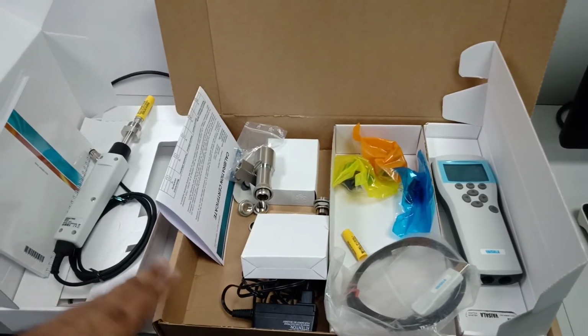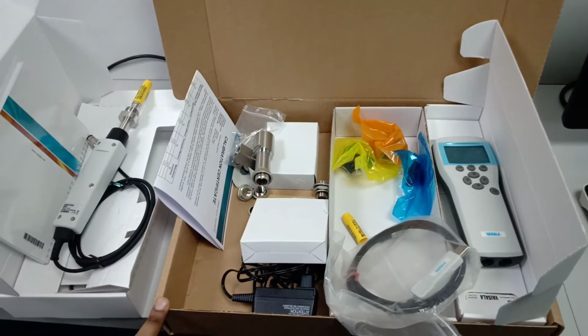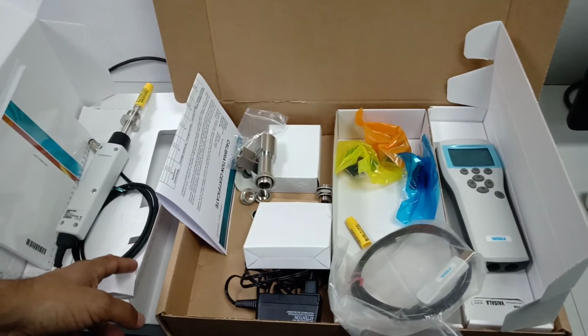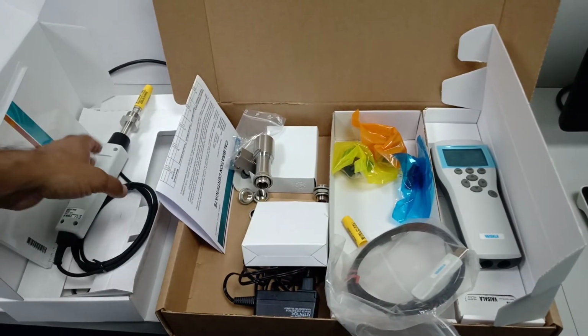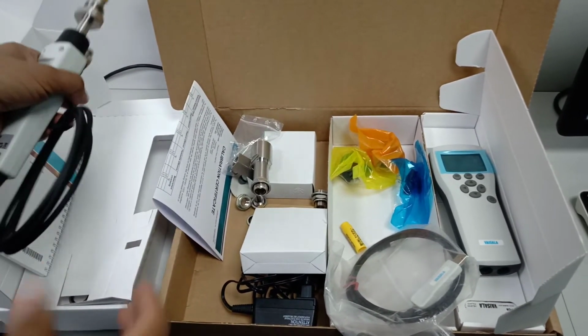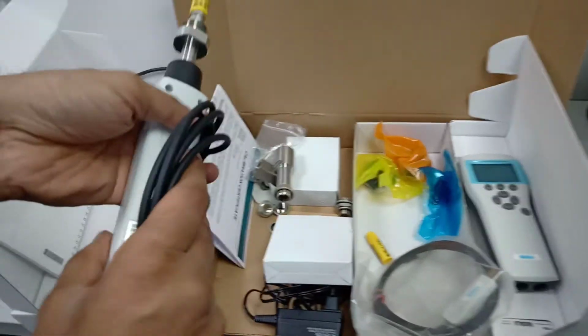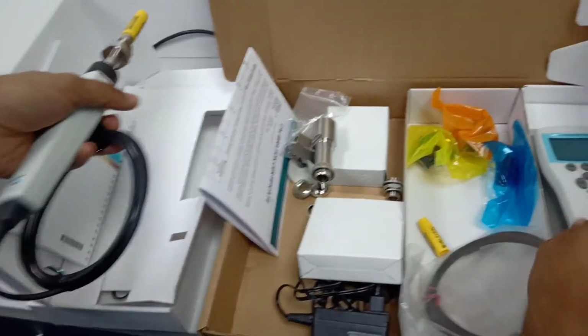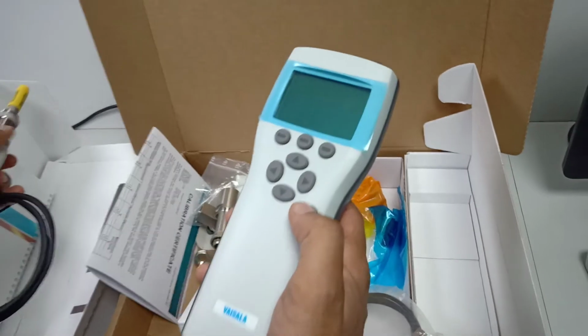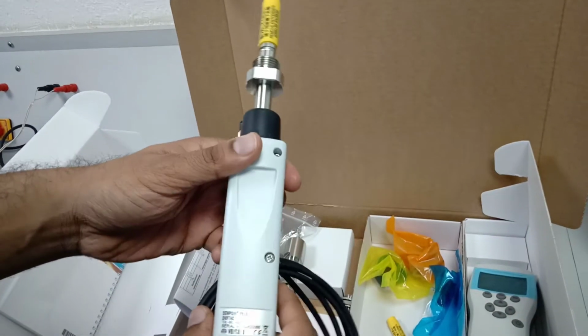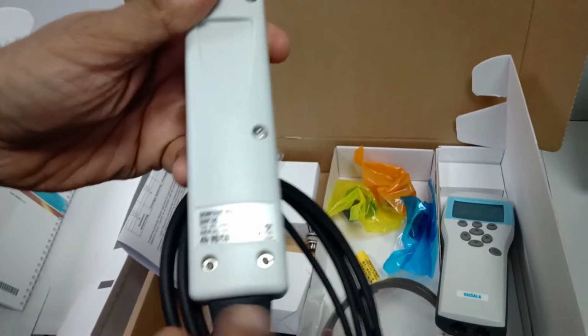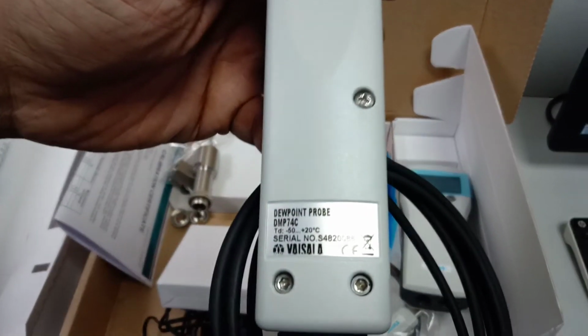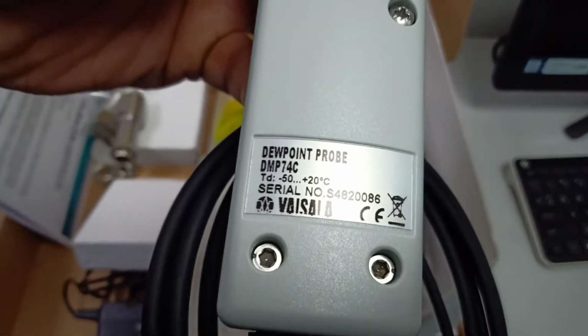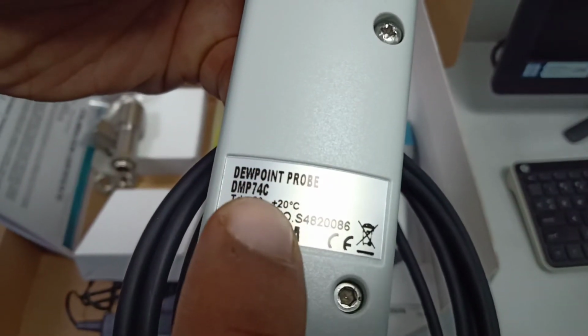So today we will be talking about Vaisala dew point measurement specifically for SF6. We have already made a video where it can be used for nitrogen and other inert gases as well. So this is, as you know, Vaisala MI70 indicator. Now this is the Vaisala probe which is used for SF6 and nitrogen and other non-corrosive gases. So this is a DMP74C probe that can be used for SF6 dew point measurement.